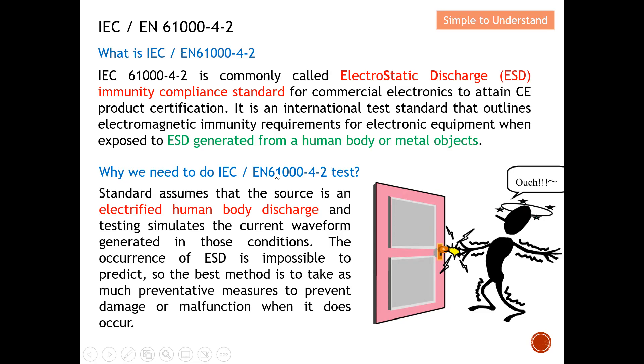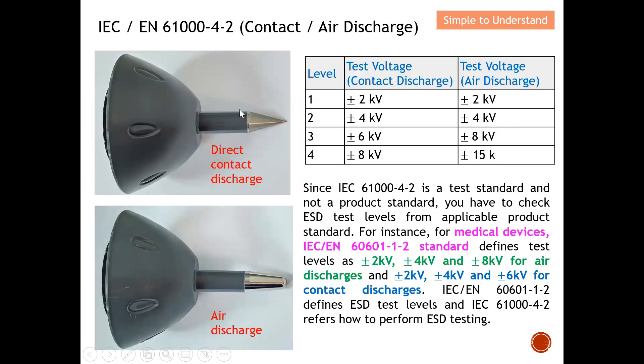There are two forms of ESD testing. The first is direct contact discharge, which uses a pointed tip on the gun head. The second is air discharge, which uses a rounded head. To identify whether it is for direct contact or air discharge: a sharp edge tip indicates contact discharge, while a rounded head indicates air discharge. Looking at the test level table, we have levels one through four, each with corresponding test voltages for both contact discharge and air discharge.